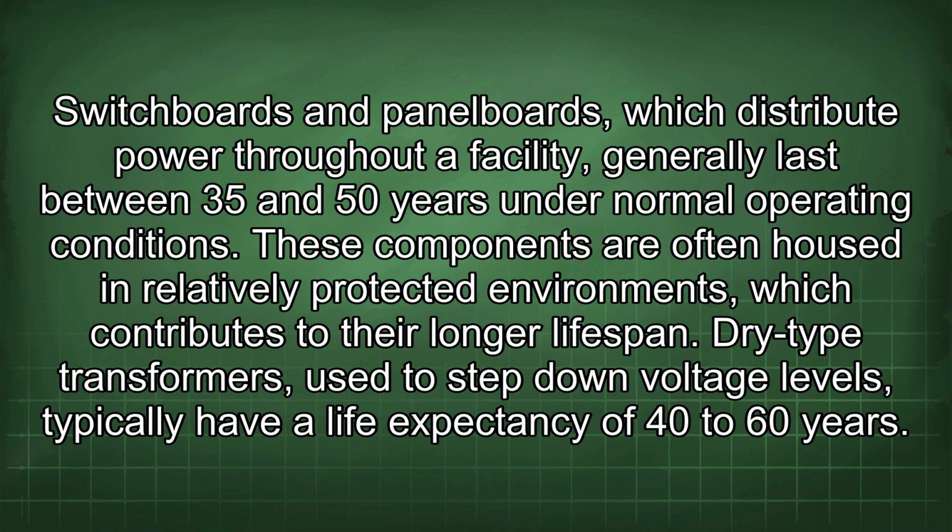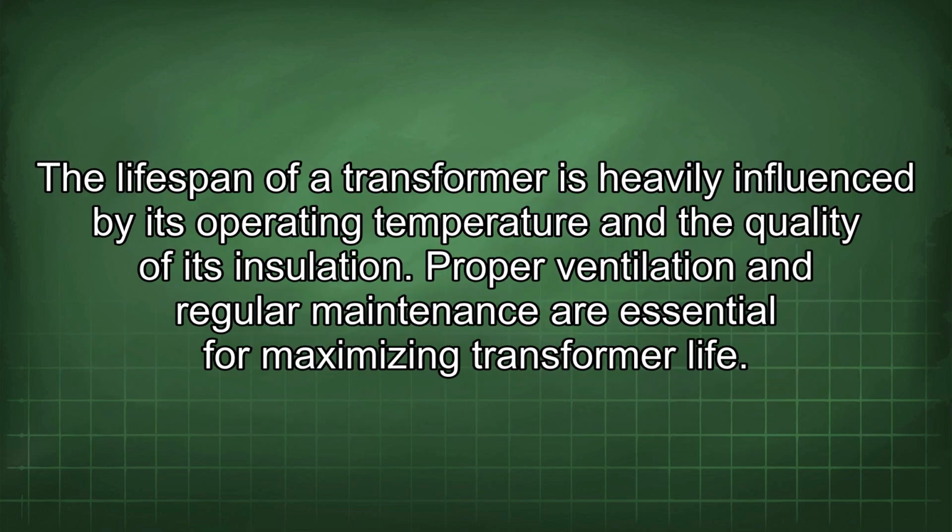Dry-type transformers, used to step down voltage levels, typically have a life expectancy of 40 to 60 years. The lifespan of a transformer is heavily influenced by its operating temperature and the quality of its insulation. Proper ventilation and regular maintenance are essential for maximizing transformer life.